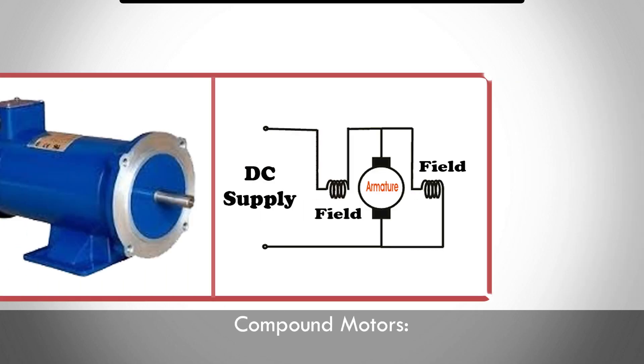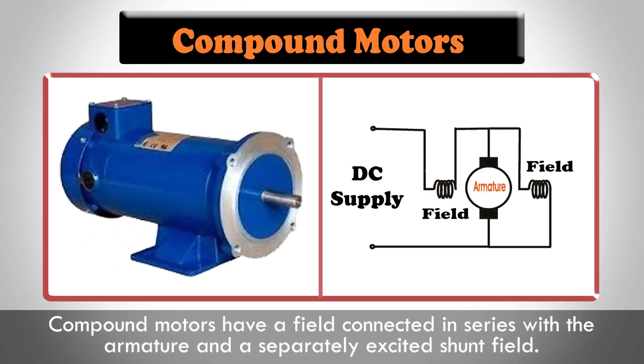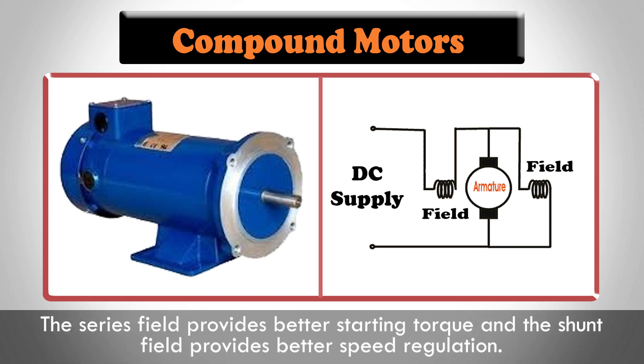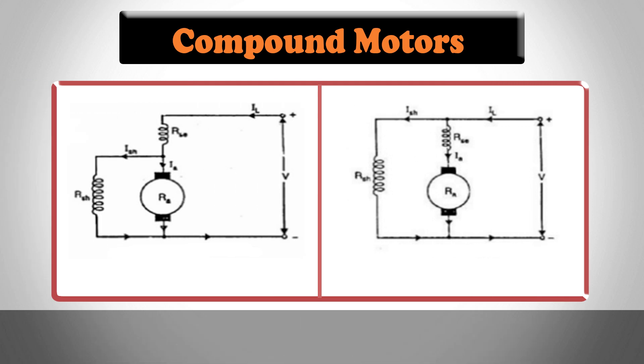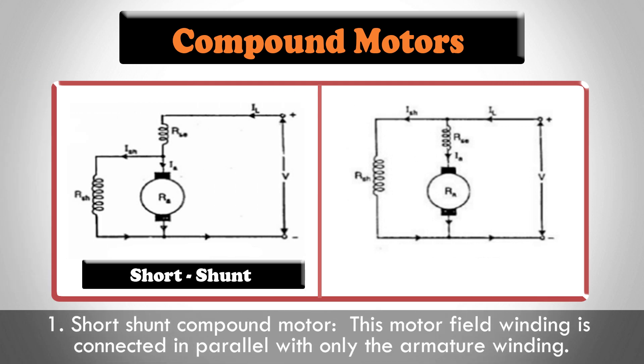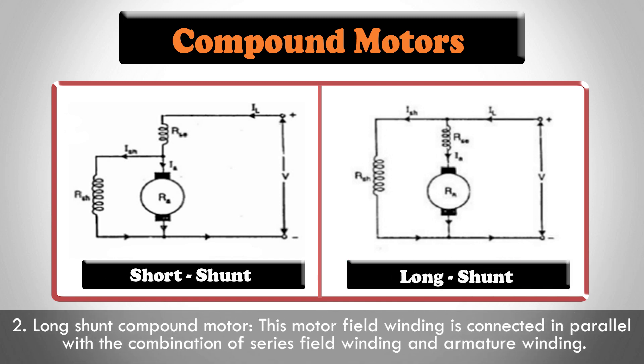Compound motors have a field connected in series with the armature and a separately excited shunt field. The series field provides better starting torque and the shunt field provides better speed regulation. Compound motors are further divided into two types: 1. Short shunt compound motor — the field winding is connected in parallel with only the armature windings. 2. Long shunt compound motor — the field winding is connected in parallel with the combination of the series field winding and armature winding.